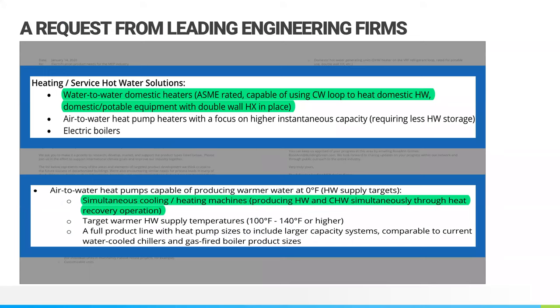Basically, it's a heat pump that allows not only heating, but also simultaneous cooling at the same time. So with the cooling effect, you get a byproduct of basically free heat. You're able to get your hot water and chilled water production at the same time. So when you're able to use these types of sources, you're getting a much more efficient transition to electrification. This is something that the engineers have been pushing for.